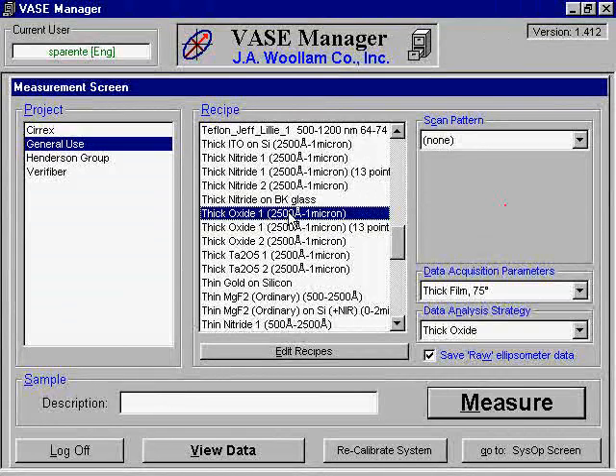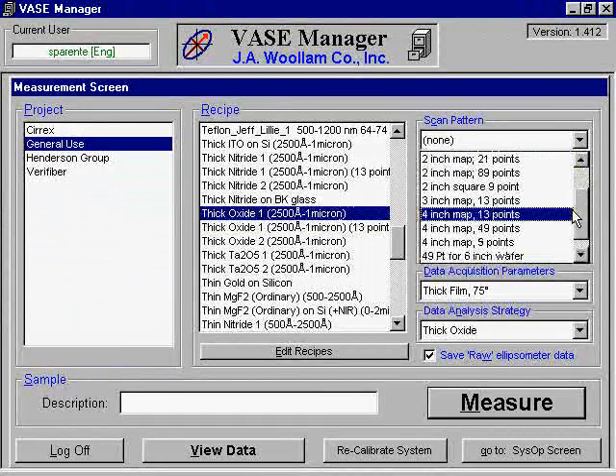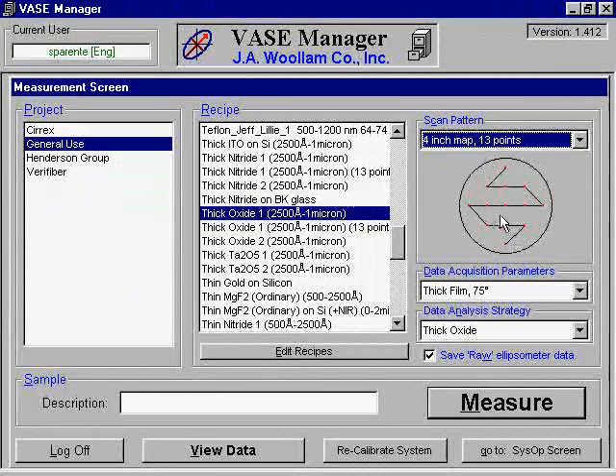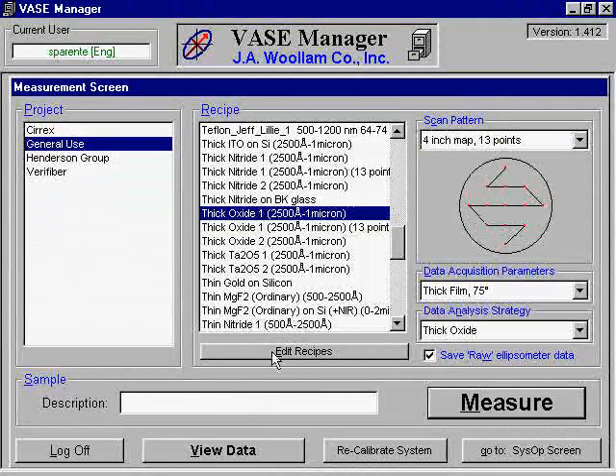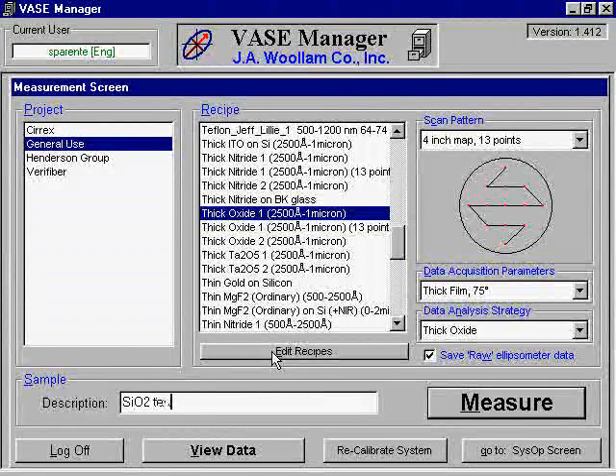The Woollam ellipsometer is capable of automatically performing scans at several designated points along the wafer. For the scan pattern, select the diameter and the number of points you wish to scan. For a single point scan, select none. For the sample description, you should enter an appropriate description of your sample, which will allow you to find it later when you wish to review the results of the scan. Once the appropriate information has been supplied, click Measure to continue.